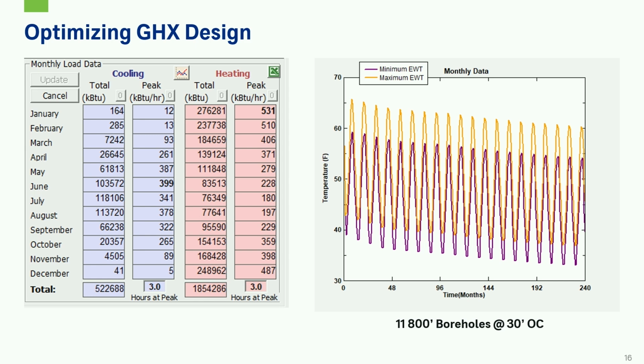Yeah, there are a lot of other configurations of the boreholes, things like that. And when we talk about drift, think about it as an energy system in which you put energy in and you take energy out. If you put more energy in, eventually you lose energy, right? So your drift will increase. So what you need to solve for is enough linear length of boreholes to make sure that your drift is leveled over 20 years or whatever interval you need.